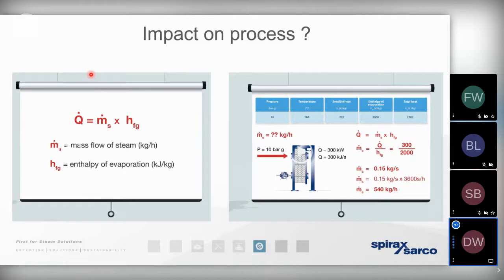This equation tells us how much energy there is in a mass of steam. So the Q value, that's the kilowatt rating, the energy content. M, that's the mass flow rate of steam. HFG, that's the enthalpy of evaporation or the latent heat. The dot basically denotes that the unit is a moving or a mass flow rate. So in other words, if we know the pressure of the steam going on to the heat exchanger, we know the latent heat. And moving across to the right of the screen, you can see that at 10 bar gauge, the enthalpy of evaporation, the latent heat, is 2000 kilojoules per kilogram.